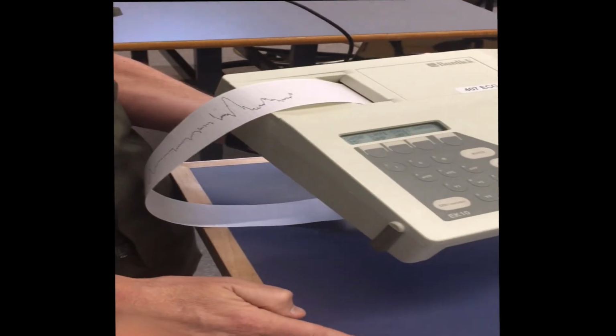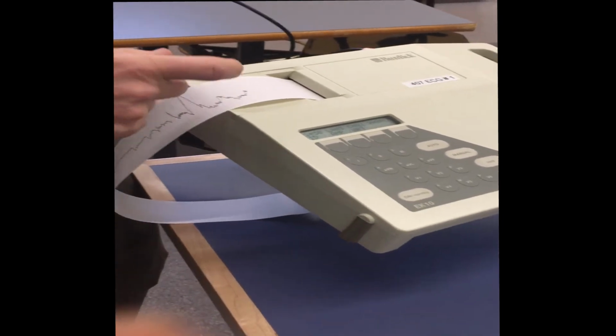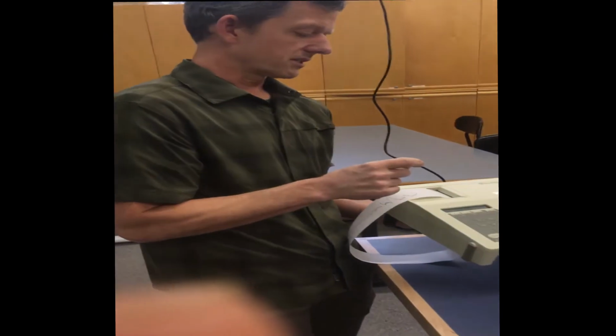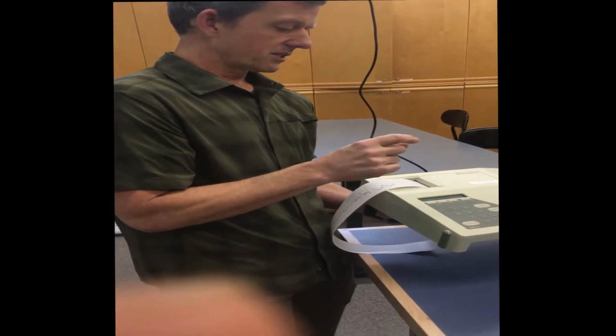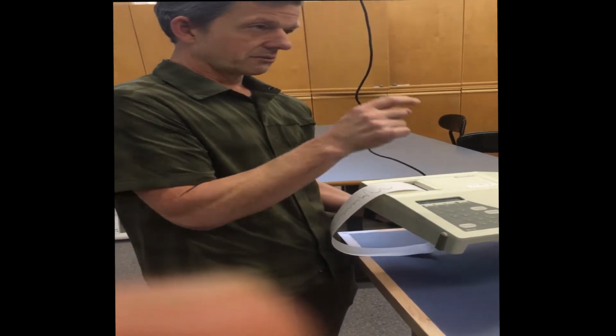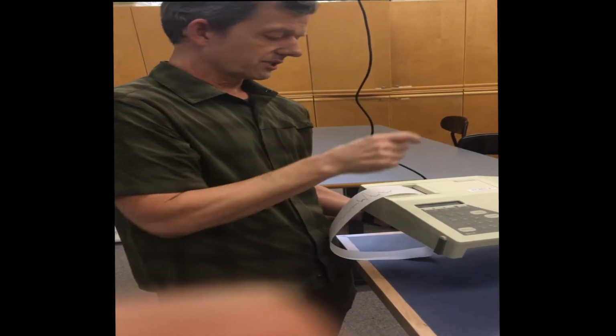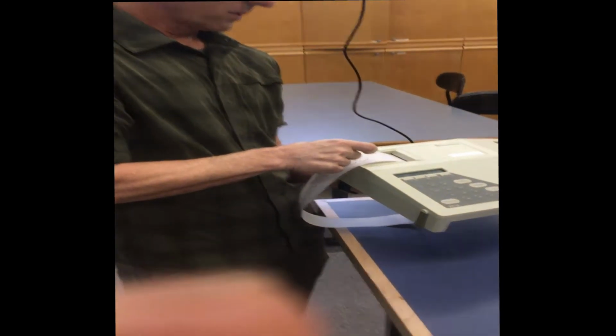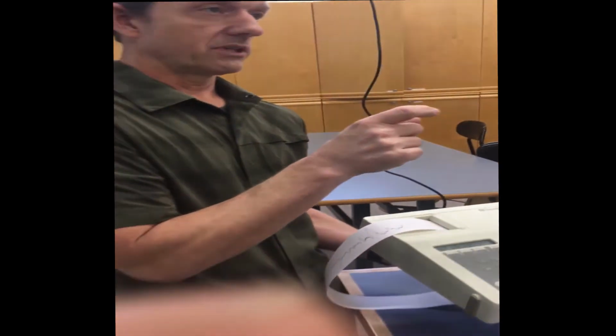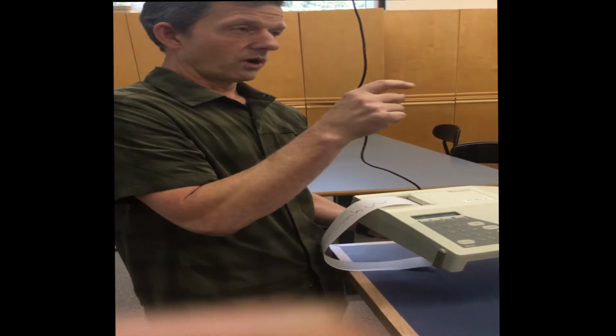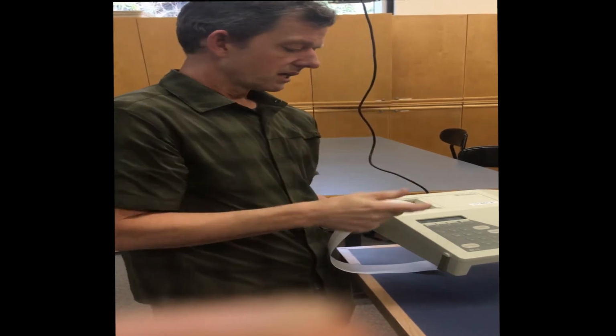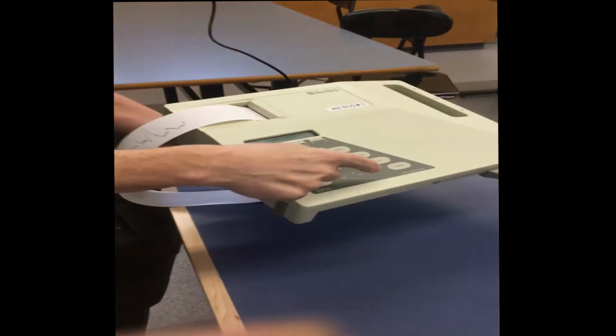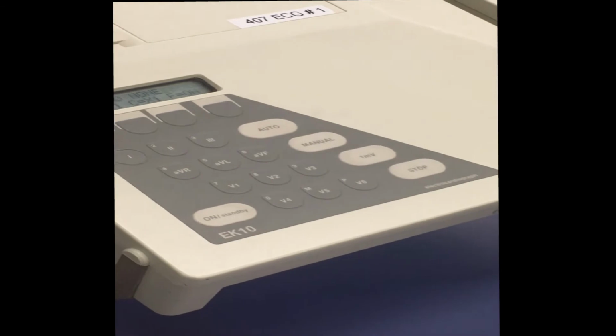The other thing that I want you to do is I want you to calibrate when you first turn on the machine. I want you to get a 1 millivolt calibration signal. So what a 1 millivolt calibration signal does is it's telling the machine that this is what 1 millivolt looks like on a piece of paper. So now if you're looking at amplitudes and you want to determine the amplitudes of complexes, you know that 1 millivolt is this distance. So when we turn the machine on, press 1 MV, and it puts a calibration square, and so now you know what 1 millivolt looks like.